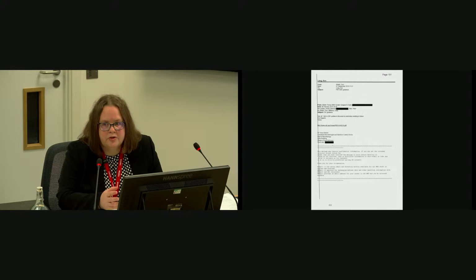So there are two things you can do with the lobby. You can have it at a positive pressure, and the room at a positive pressure, and that's what we would call a positive pressure cascade, which means the lobby is at 10 pascals and the room is at 20 pascals. And that's giving the patient an extra layer of protection. So the air is effectively moving from the patient's room out through the lobby to the corridor?